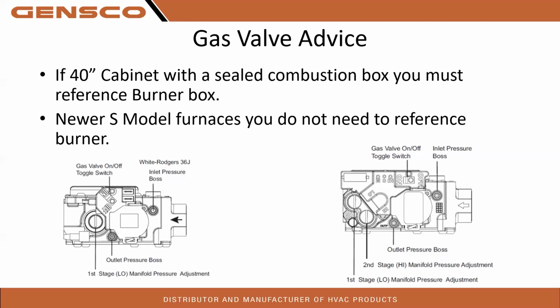So on the left, it's the single stage. So you have the little brass or sometimes aluminum, depending on the valve manufacturer. Most of them are brass. You have your first stage low manifold pressure adjustment. So you remove that cover. You can make your adjustments to your pressure, and then you can put the cover back on to make sure it stays accurate. Or most technicians just put their thumb over it to make sure it's stable before they put the brass cap back on.